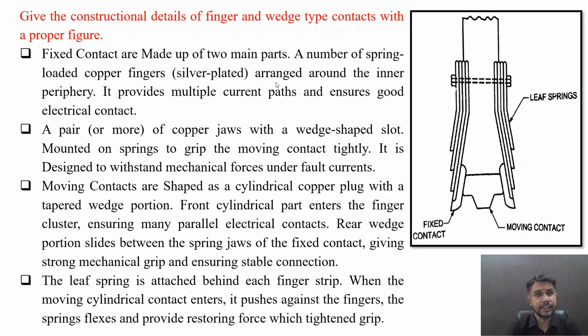Explain the constructional details of finger and wedge type contacts with a proper figure. Fixed contacts are made up of two main parts. One is a number of spring-loaded copper fingers, silver plated, arranged around the inner periphery. It provides multiple current paths and ensures good electrical contact. The other is a pair or more of copper jaws with wedge-shaped slots mounted on a spring to grip the moving contact tightly.